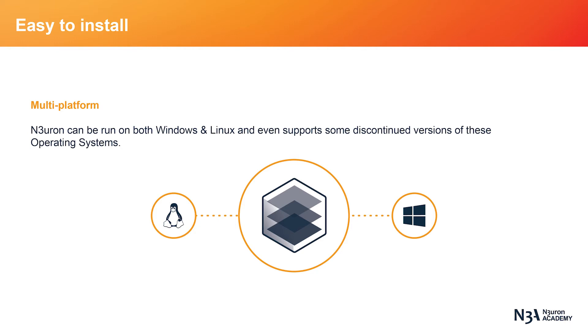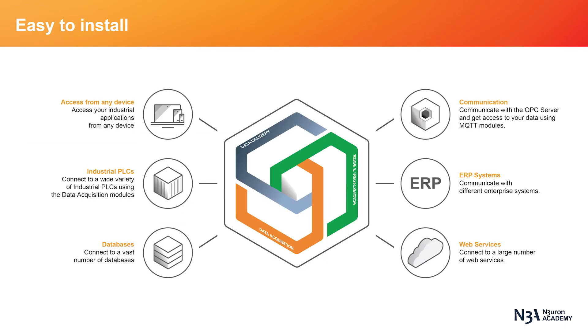As a web-based software solution, you can access and configure Neuron from any device. Neuron's core functionalities lie in its fully integrated software modules, which allow it to function as a communication hub. Its OPC UA, DA, and XML client modules allow you to communicate with virtually any OPC server, making it possible to communicate with almost any PLC available on the market. Additionally, Neuron's OPC UA server module enables data exchanges with any other third-party OPC UA client. Neuron also includes the MQTT client module, allowing users to connect the platform to any MQTT brokers for fast and efficient data access.